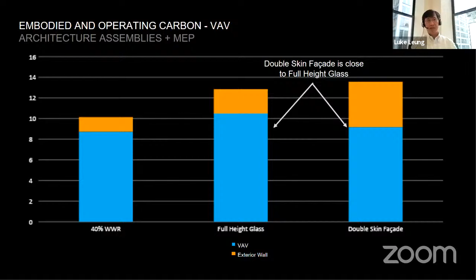Similar for VRF systems—actually slightly better in this case, because on the heating side VRF is much more efficient; the COP is much better than a boiler in a VAV. The point is, once you start looking at whole life carbon of the entire HVAC system and facade, you'll reach a very different conclusion when you integrate the facade, HVAC system, and refrigerant leakage.